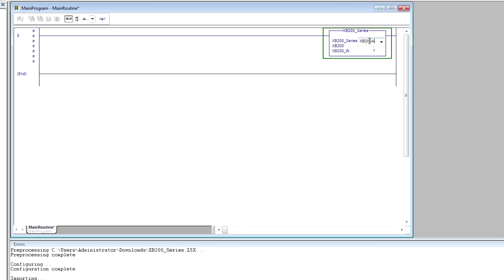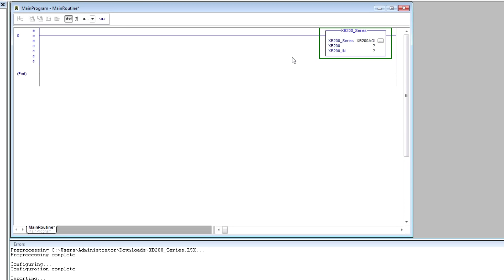So configuring instructions requires creating a few tags: one for the instance of the add-on instruction, one where I define the input tag that comes from the generic Ethernet module we created previously, and one for the output tag, which is the tag we'll use based on our UDT that has the meaningful data.